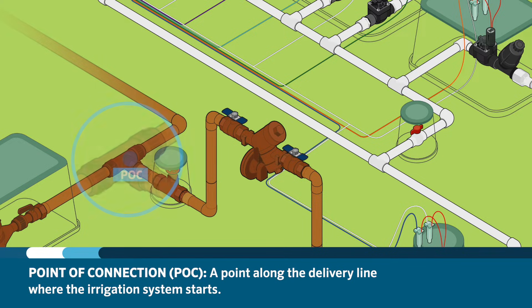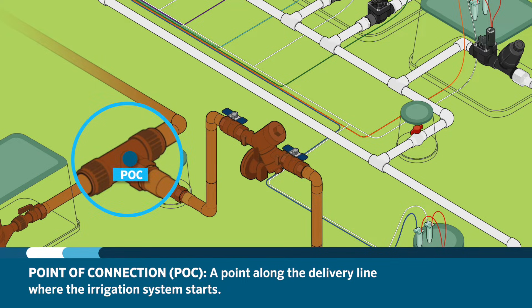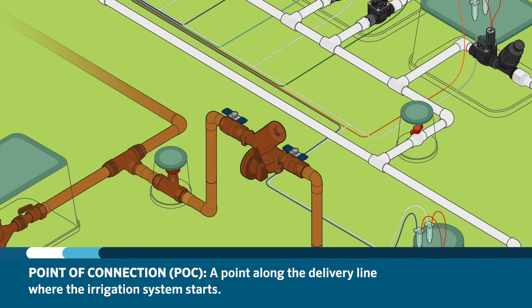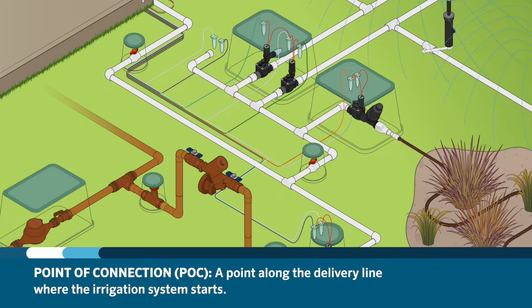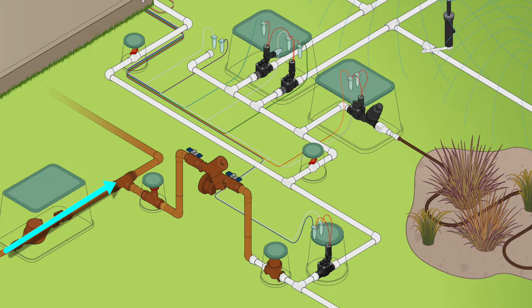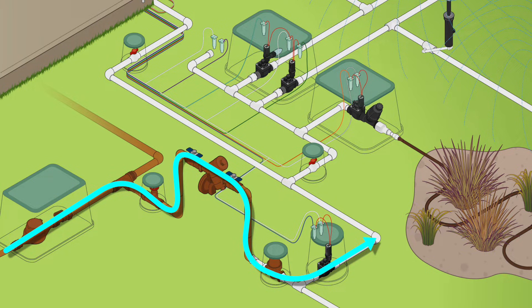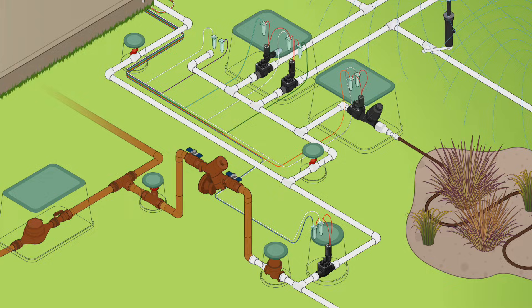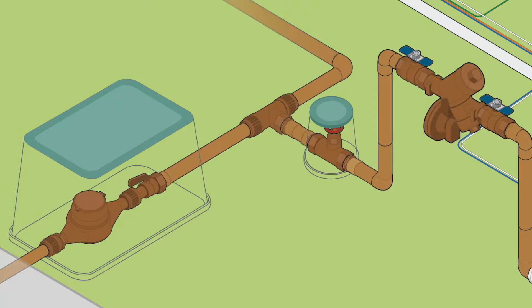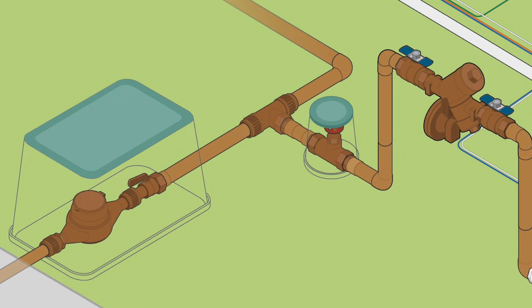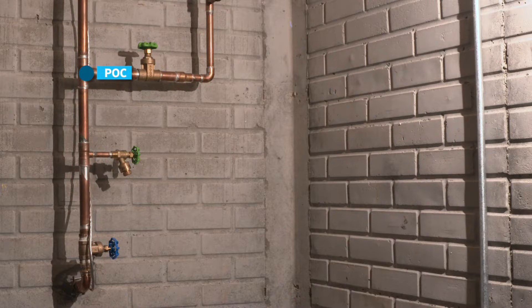After the water meter, the water moves through the delivery line to provide water to the house or building. A point along the delivery line is chosen to be the point of connection, or POC, for the irrigation system. Typically, this is where the irrigation system starts. Water is directed to the irrigation system from the delivery line that supplies water to the home or commercial building. This will be different if the irrigation system has a dedicated water source separate from the meter. In warm climates, the POC is usually before the building, and in cold climates, the POC could be inside the building.